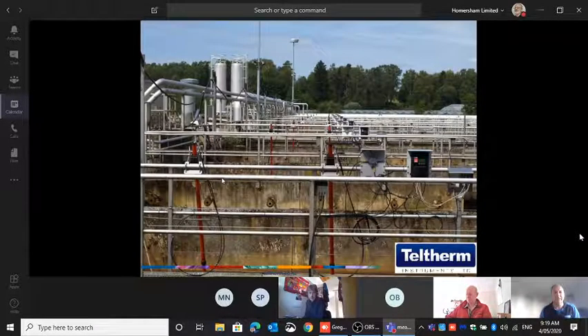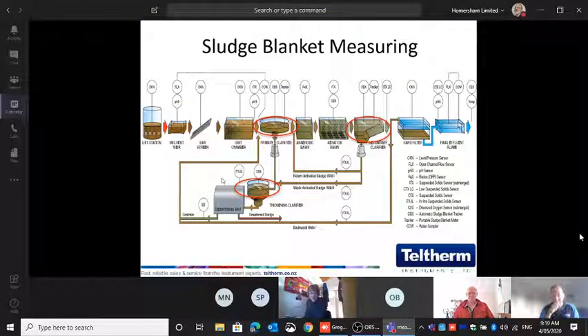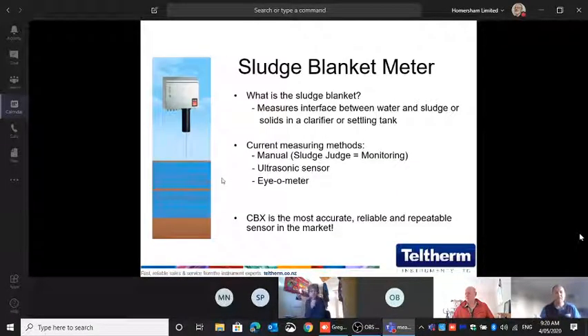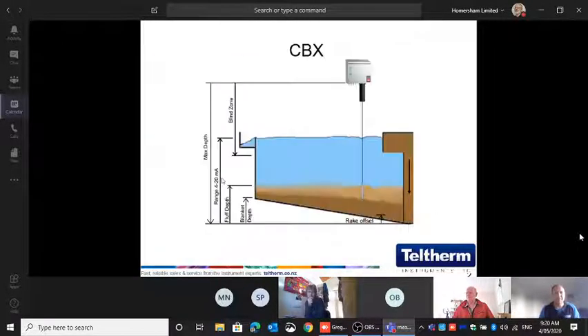This is what we would like to see in the wastewater treatment plants and water treatment plants. But yeah, this is a bit bigger. This is not us. Now your sludge blanket unit. The sludge blanket unit uses the same sensor. Yeah. What people currently use is a sludge judge, an ultrasonic sensor, or what we call an iometer. Basically, they just look. Well, that works most of the time. The problem is if you get the problem, this is what you want to see.